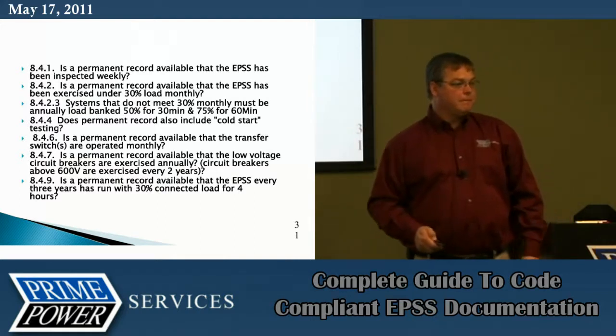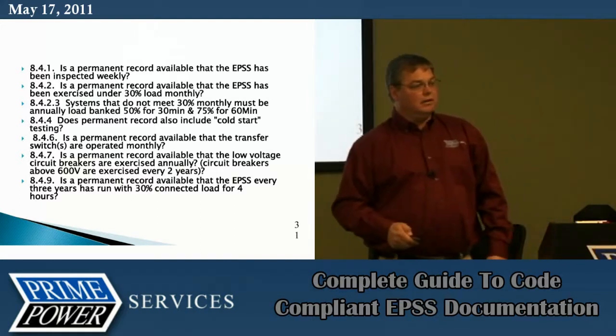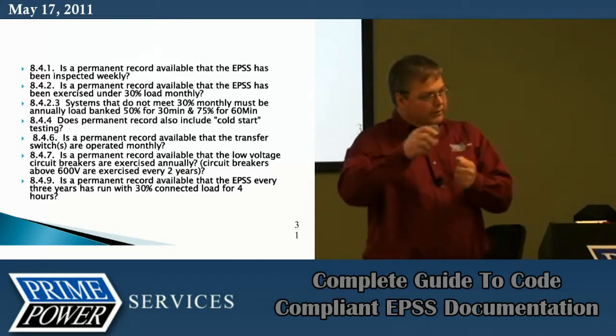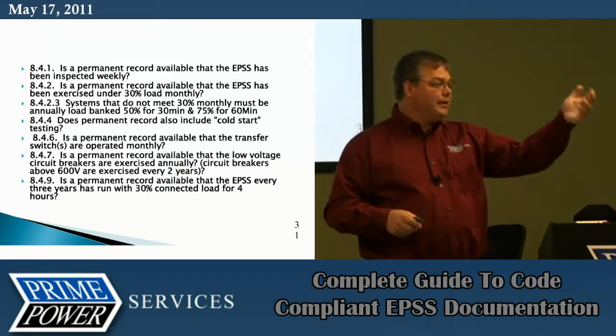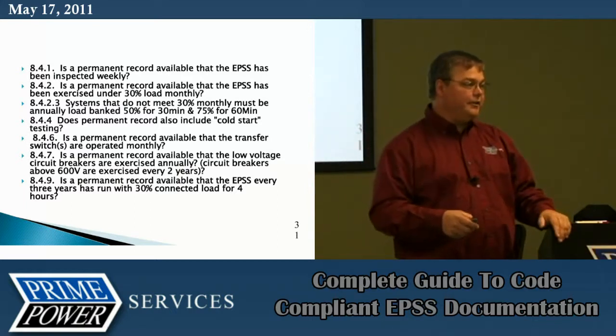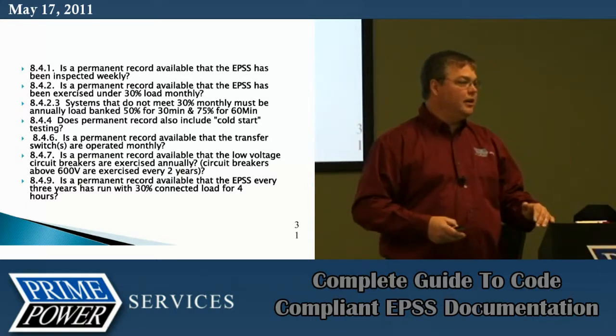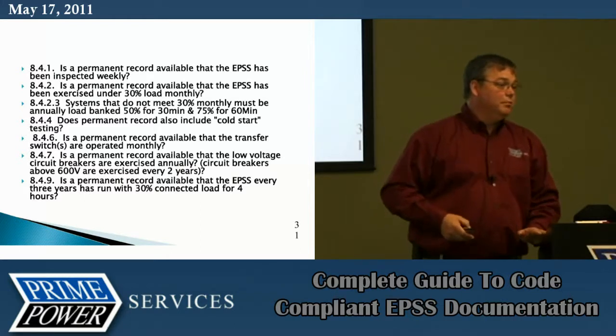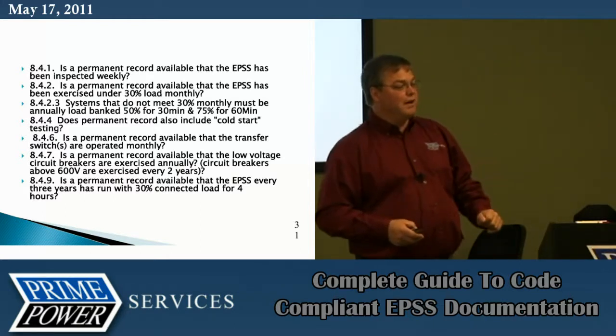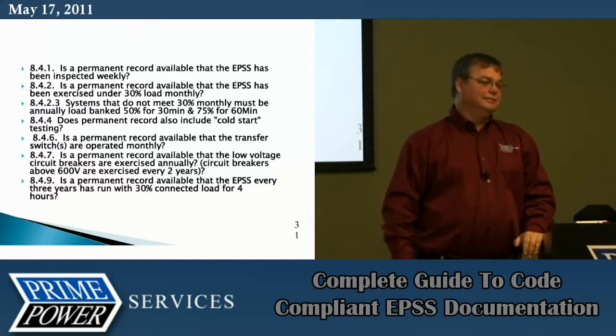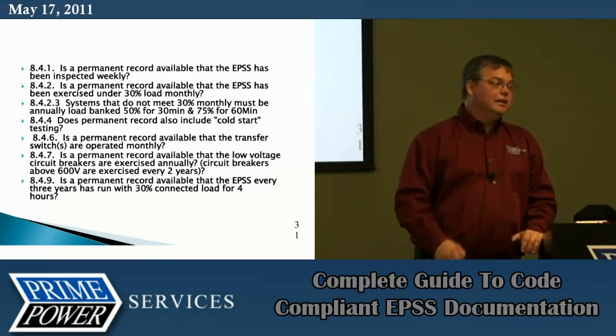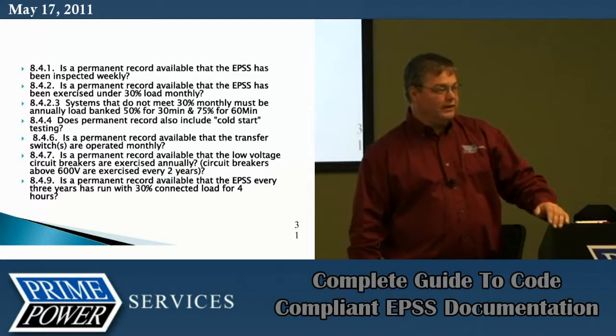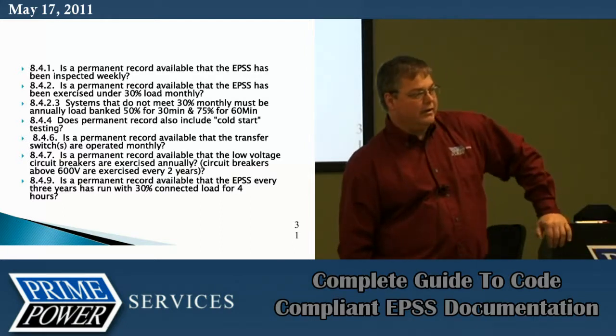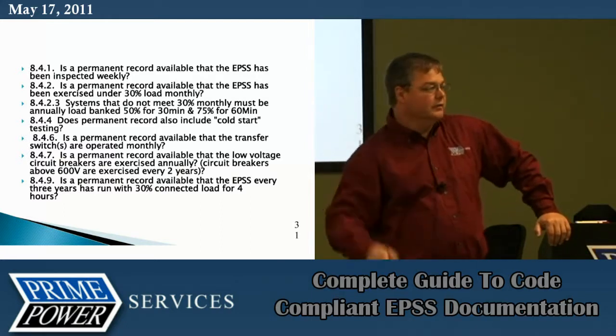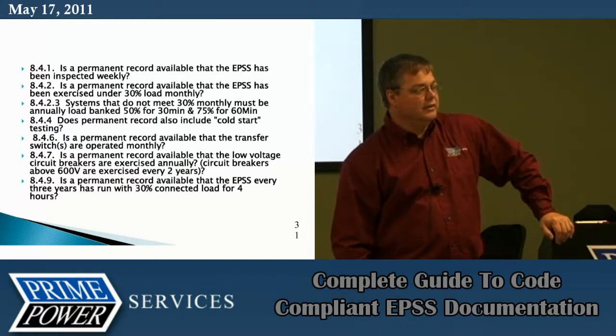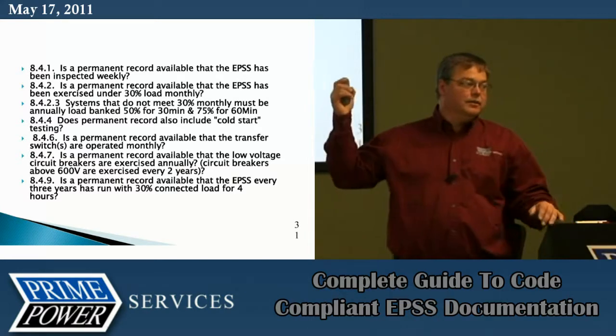How do you document that - how you start the time frame? If you're doing your readings and you fired it at 3:30 in the afternoon and take your first reading at 3:32 and it's got a load on it, that's documentation enough. Unless you wanted to note it was your cold start test running at 3 o'clock. You can look at the meters and time and over-analyze it, but generally the records from a month to month run are acceptable if you're doing it on that regular schedule. I've never gone back and asked anybody for this one.